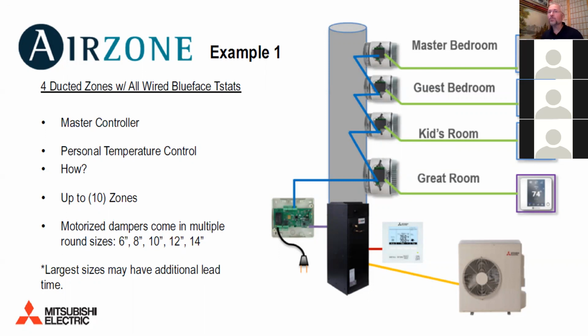So AirZone, next solution. You can see on this picture, this is what I imagine is the anticipated primary way that AirZone is used for Mitsubishi equipment. In practice, I've actually seen more complicated systems than this. You have an AirZone control board that plugs in from our communication board to the CN105 port on any indoor unit. Here it's depicted connecting to an SVZ air handler. Then dangling off of the MA 2-wire connector is a PAR 40. You're going to want to use a Mitsubishi controller to commission the system before turning on the AirZone, just to make sure there's no errors.